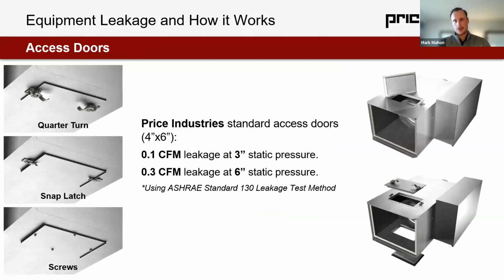So we did testing for our access door, and we're going to start to put this in our specification. It's something that's going to happen by summertime. I'll talk about why there's a little bit of lag there. But Price Industries quarter turn snap latch, or screw access doors perform quite well for leakage. 0.1 CFM at 3 inches of static pressure, 0.3 CFM at 6 inches of static pressure. This is using the ASHRAE Standard 130 leakage test method. So essentially installing the terminal as you would in an actual install, taping off all the seams and taping off ductwork seams and transverse joint seams, and just specifically looking at leakage only through the seams of the access door.